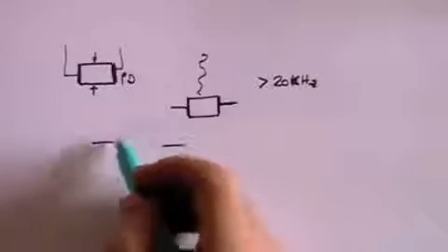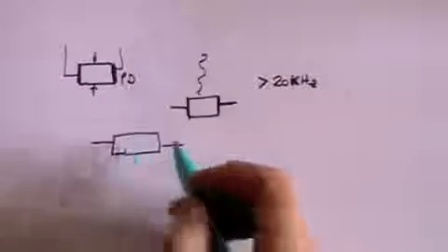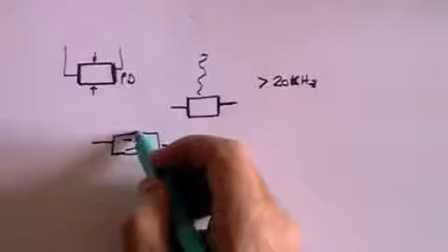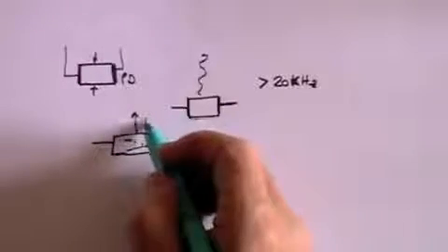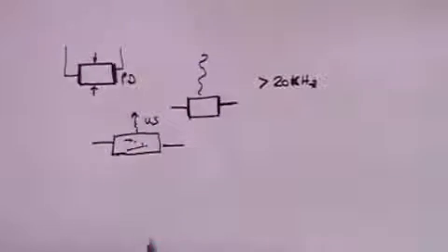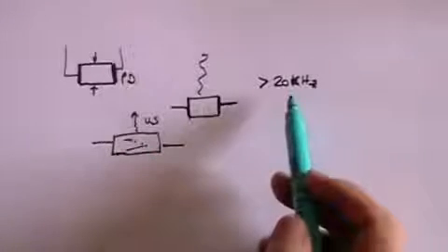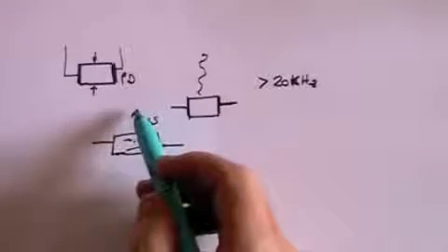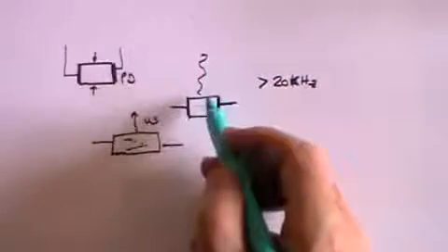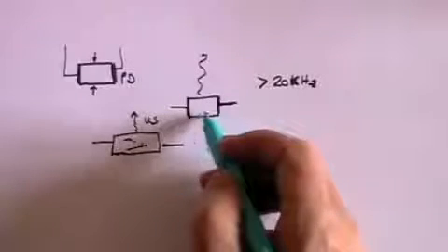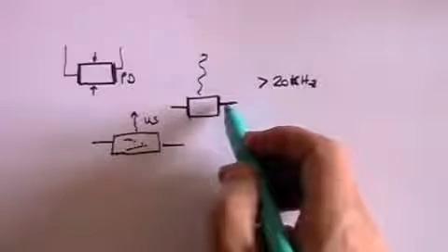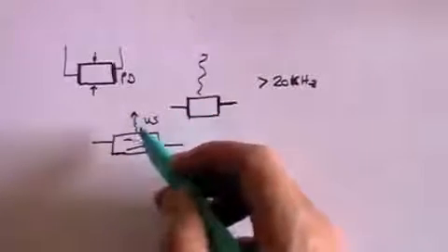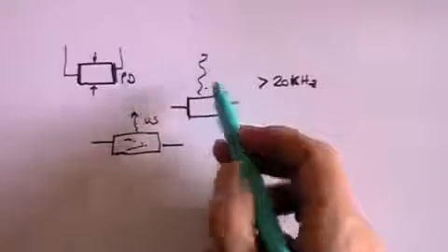If you actually pass an electric current through the crystal, it will cause the atoms in the crystal to vibrate, and those vibrations will come out as ultrasound. That is, the frequency of the vibrations is just over 20 kilohertz. So that's a way that you can create the sound. Similarly, if you've got sound coming in, it will cause the atoms to distort, and that will create a voltage, and that can be detected. So the same piece of equipment both generates the ultrasound and detects the ultrasound.